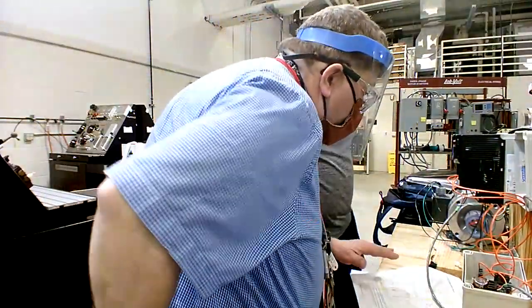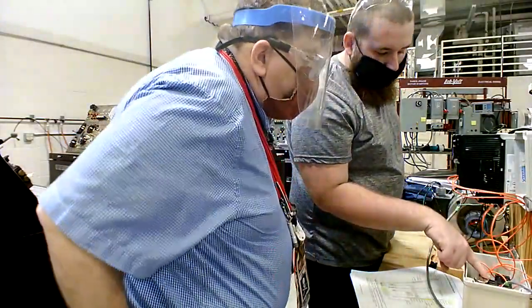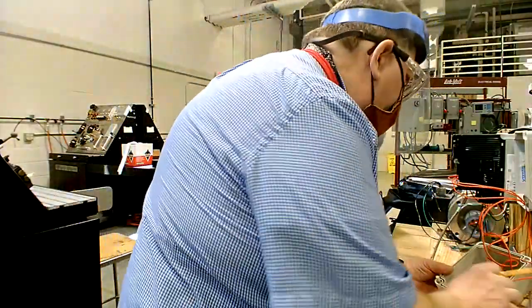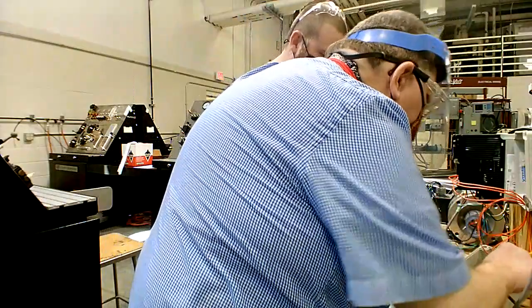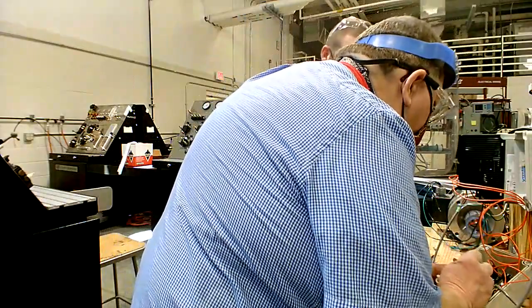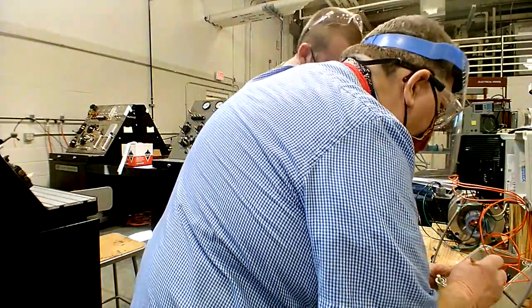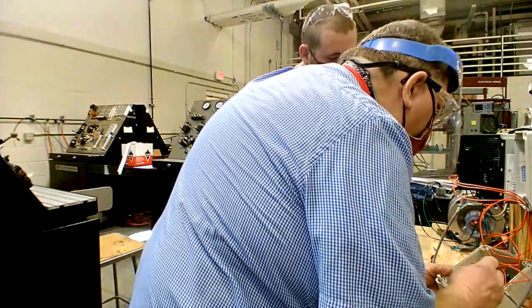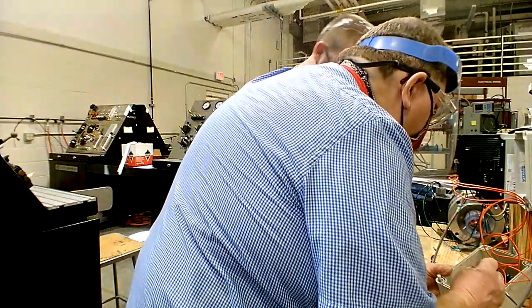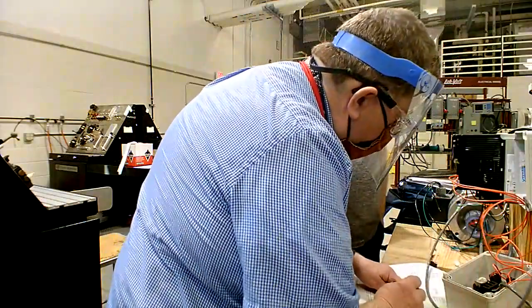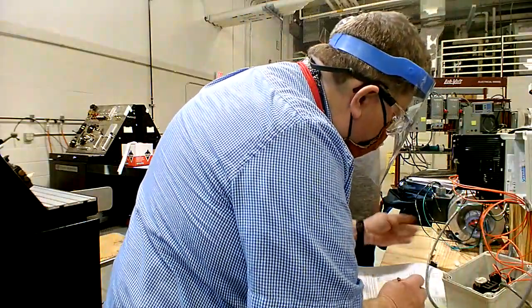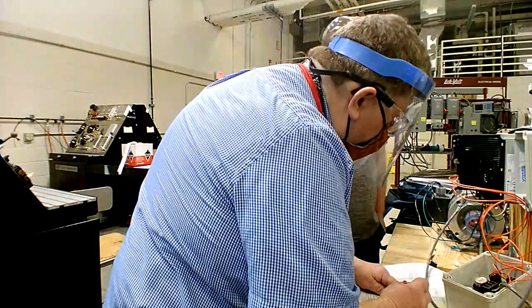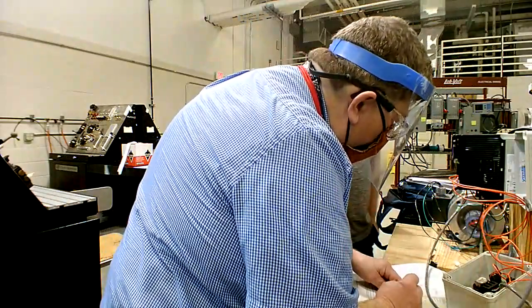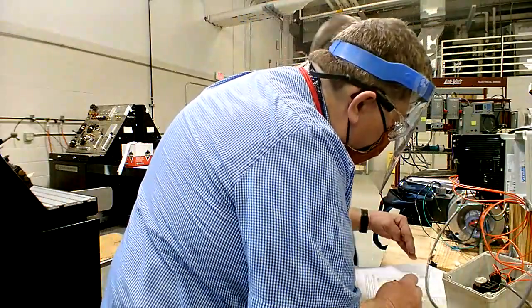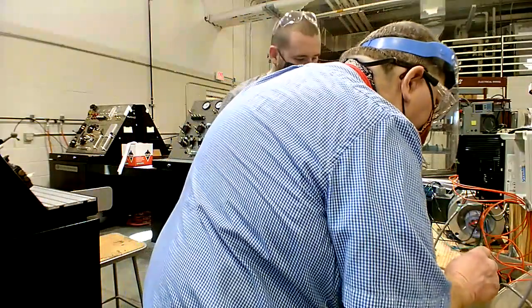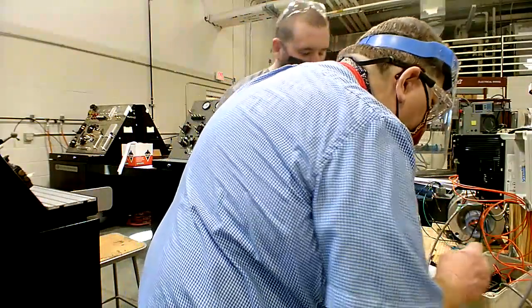All right, so all that's good. So that's correctly wired in here as well? It is. Now the orientation of it, I know it is correct. Well, no, your red has to be on the outside. The clear is the wiper in the middle. That's your 0 to 10 signal. Red is the 10, and then 14 is a common 0, so you'll have to flip the red and the clear. You have to flip those two.